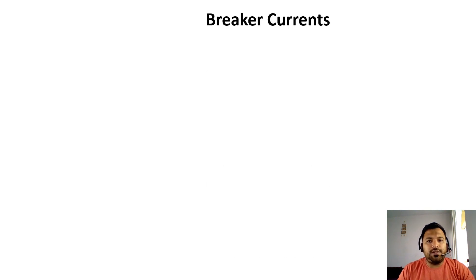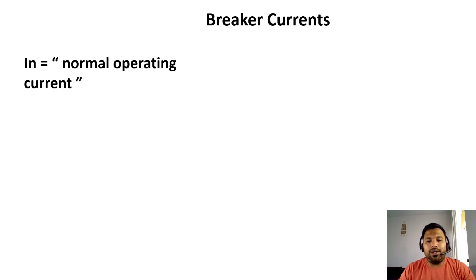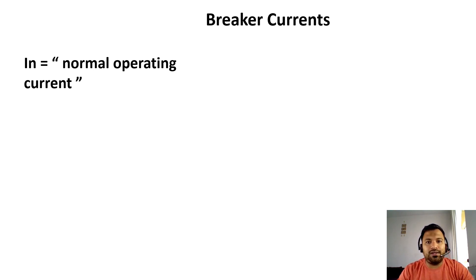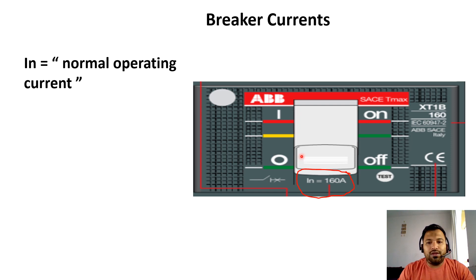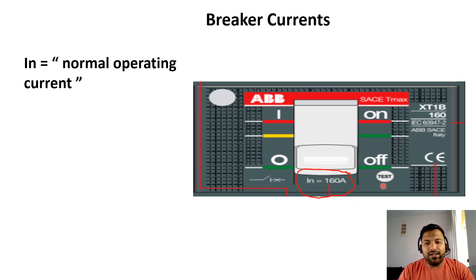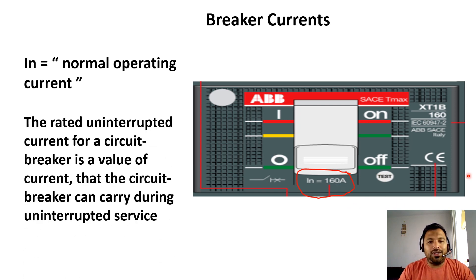Breaker currents: the first one is the IN current. What is IN current? At the circuit breaker, at normal operating condition, how much current will flow — that is called the IN current or normal operating current. If you see this particular circuit breaker, IN is equal to 160 amperes. So this circuit breaker's normal operating current is 160 amperes. The rated uninterrupted current for your circuit breaker is a value of current that the circuit breaker can carry during uninterrupted service.